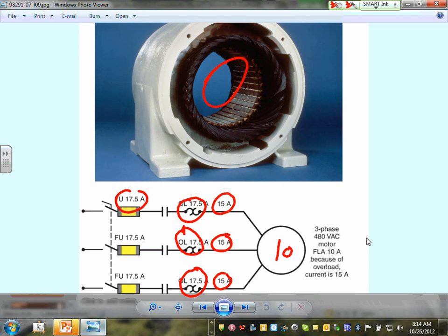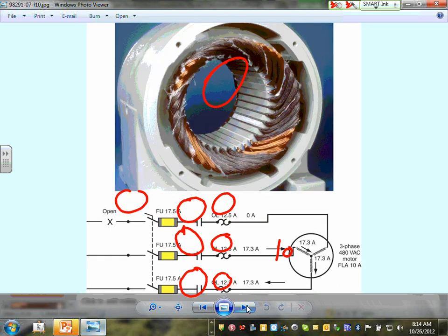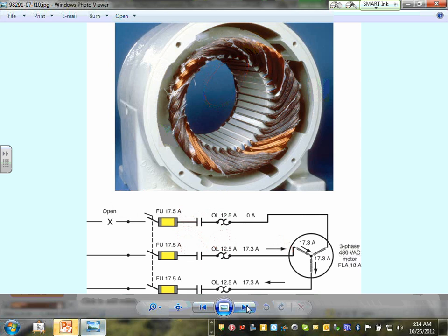If this is a big motor, here's $500. Bigger motor could be thousands of dollars. Can I emphasize, guys, the importance of the overload? So I thought that will bring it home to you, and how to size it appropriately. Where did they get that 17.5 from for the overload? Somebody sized it wrong. Wrong. Okay. Yeah, they were sized wrong.